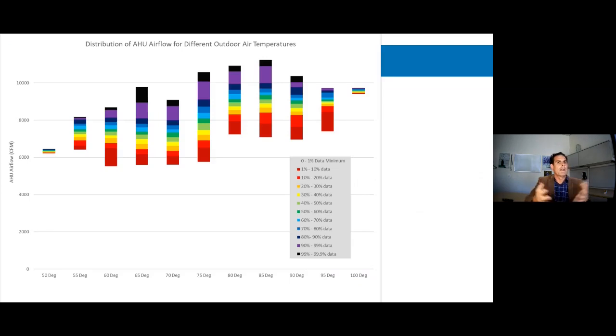This is another air handler historical graphic. This one's a little prettier because it has rainbows. But another useful way to look at that data is to round the outside air temperature into 5-degree bins. So each one of these rainbow stacks shows the distribution of CFMs in a 5-degree bin.